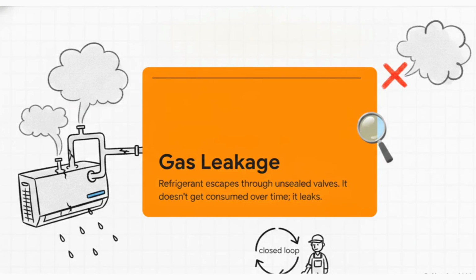But what if the filters are perfectly clean, the fan is blowing strong, but the air coming out is just room temperature? Okay, let's clear up a massive misconception right now. Gas does not get consumed over time like fuel in a car. It operates in a completely closed loop. So if your AC is low on gas, it leaked, period. Refrigerant escapes through unsealed valves or damaged connections. Honestly, if a tech tells you it just naturally needs a yearly top-up, they aren't fixing the root cause.